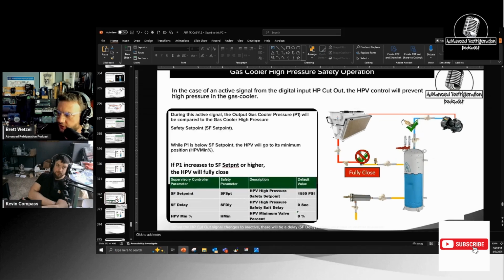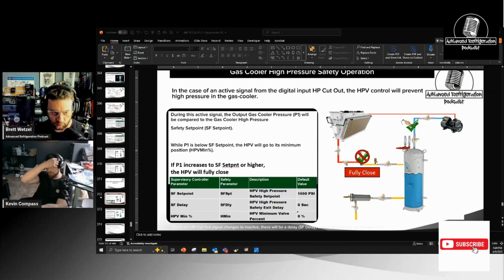You're talking about the solid state ones, yeah? Yes. Those solid state relays, I've seen them intermittently fail and cause HPV issues because it's constantly throwing the iPro, the Danfoss 326A, into startup and shutdown, startup and shutdown. It's less bad with the iPro because you can graph it. The 326, you can't graph it, so you end up seeing the startup and shutdown signal nonstop on the 326, and it may be causing head pressure issues.